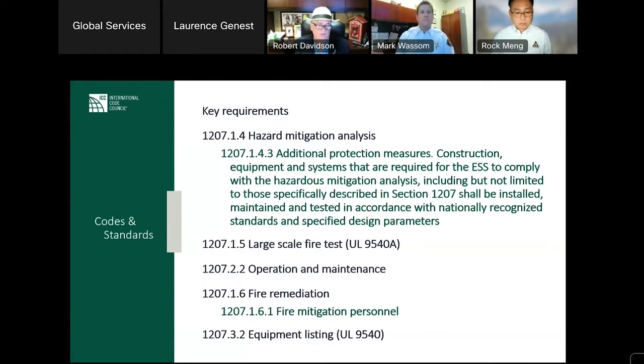One of the key things important to the fire codes, both in 855 and the International Fire Code, is fire mitigation personnel. In other words, these events are going to be long, right? They virtually burn out, and then they have to cool down. And instead of the fire departments being tied up with their personnel at a scene, we require fire mitigation personnel be provided by the site to alleviate them. And these people have to have a higher level of knowledge. They have to have knowledge of what they need to do. Next slide, please.